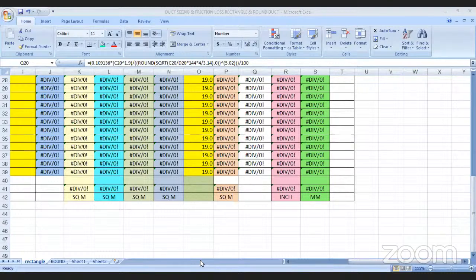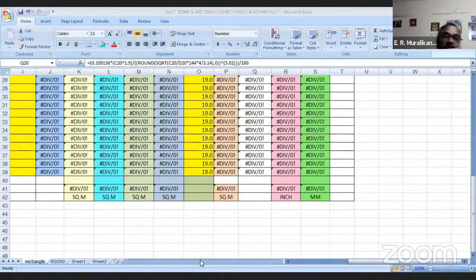How can we calculate electricity saving by duct leak sealing? See, there is no exact scientific formula to prove how much energy saving there will be. But as I told you, the return duct is the biggest culprit. Supply leakage is easily visible, and instead of 1000 CFM, you may get 900 CFM in the room. It's not a big thing. But the return duct contributes a lot of heat load because in the vacuum it pulls a lot of unwanted heat from various surroundings. So as long as your return duct is leak tight, you have an energy saving.